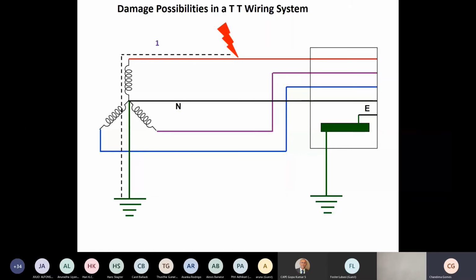And don't forget that in this case, the transformer has a very high impedance due to the coiling. And therefore, most often the current will flow in the form of an internal arc inside the transformer between the coils. Or there is another way: you can have an arcing at the wire, the line itself, from the line to the neutral, and the current may flow through the star neutral point at the transformer. And also, this is what happens most often when lightning strikes close to your building.